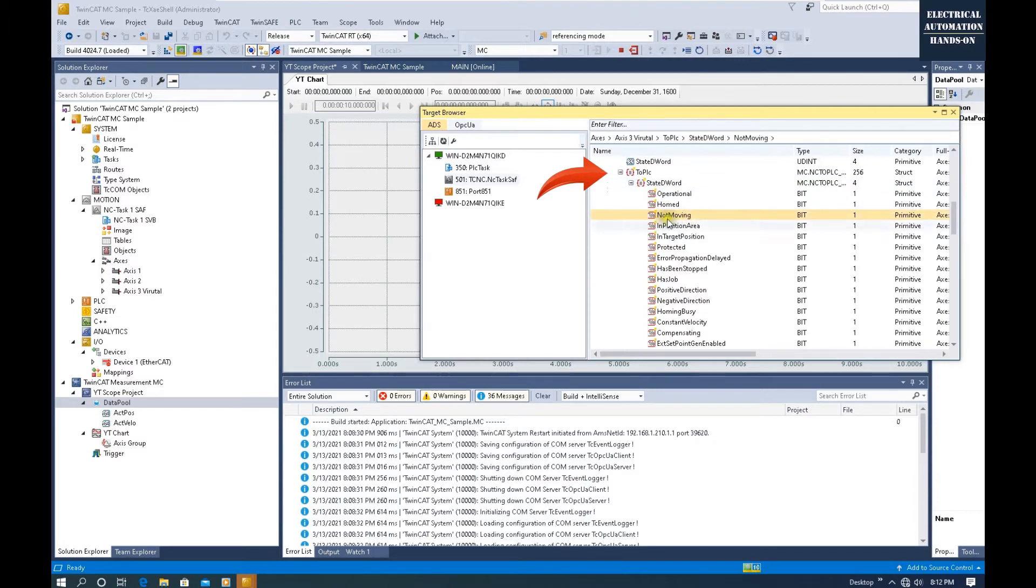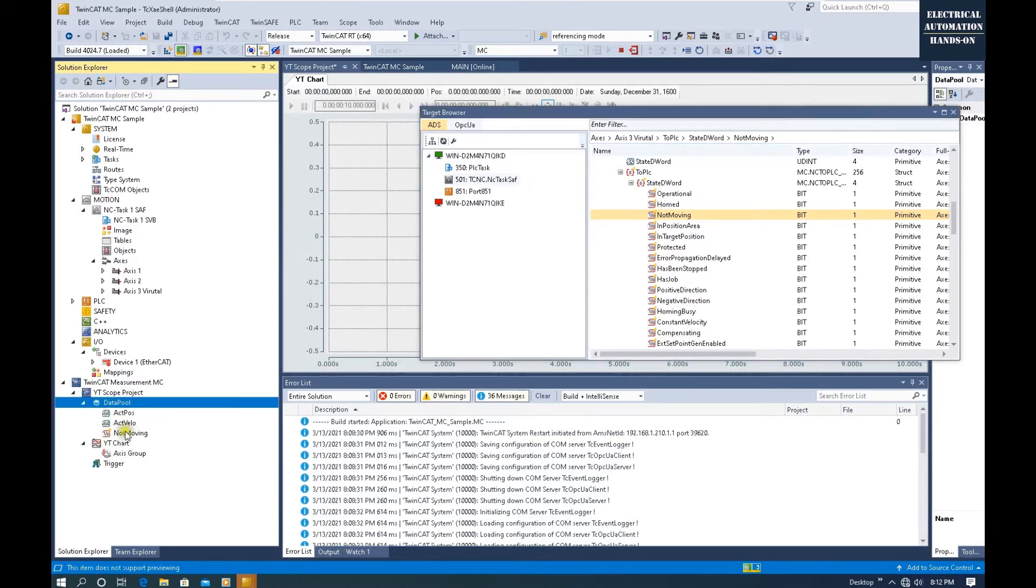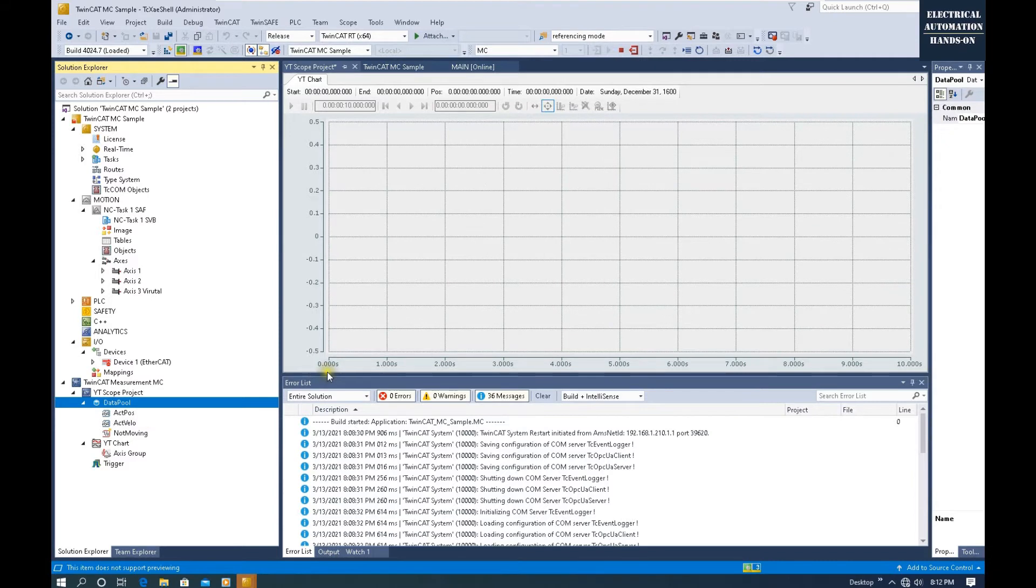Let's expand here: To PLC, Status, the word. Within this word, we will see this bool 'Not Moving.' So once on, that means this axis is not moving, it's in standstill status. We can grab this Not Moving to the data pool.